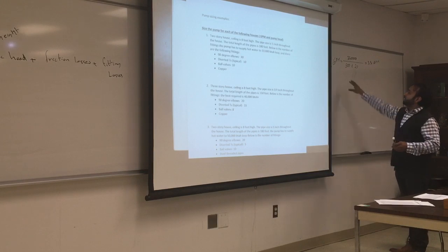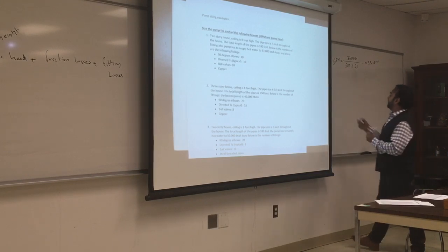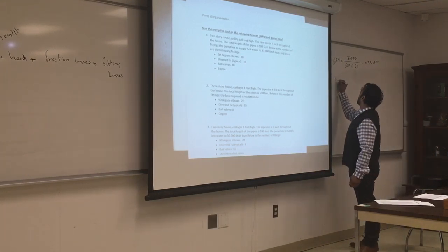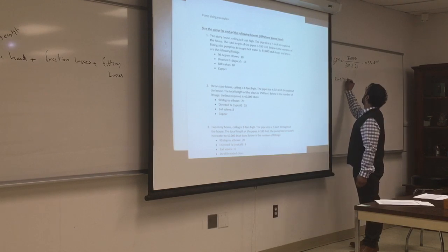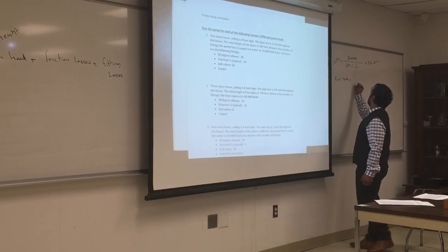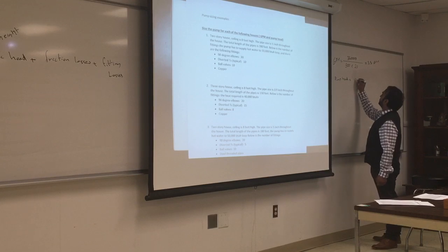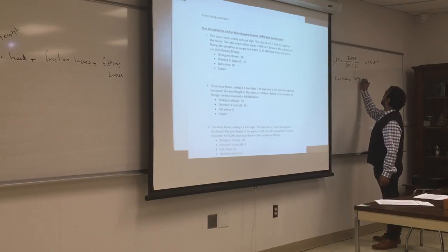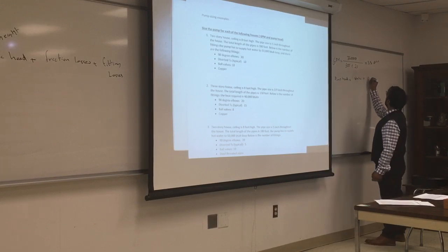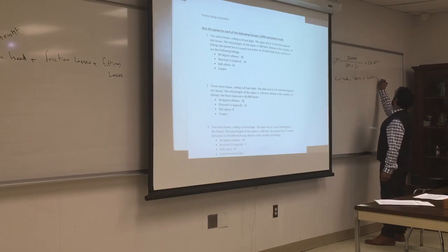3.3 gallons per minute. Okay, so we got the GPM. Now we have to find the pump head. Pump head equals static head plus friction plus fitting.